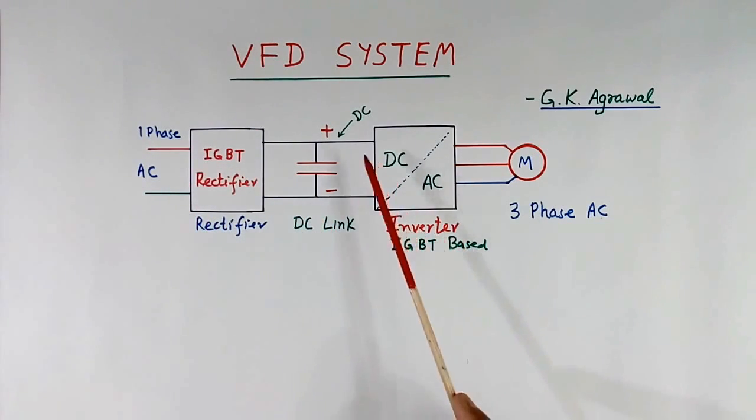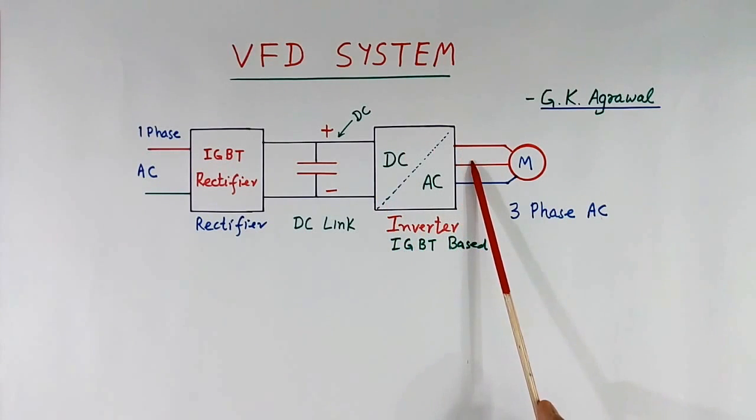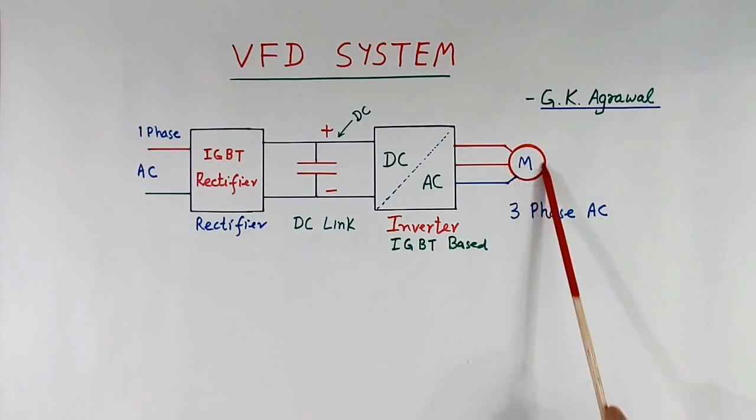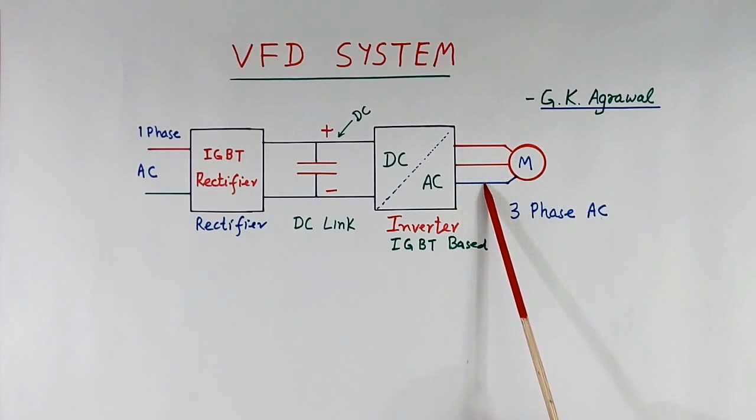Inverter converts DC into 3-phase AC. This also nowadays is made using IGBT. Now to control the motor speed, frequency of this AC supply needs to be controlled. That also is done by this inverter. So inverter does 2 jobs mainly. One is to make 3-phase AC supply. Second is to control the frequency. But in traction system, there will be so many controls, but simplest one is to control the frequency here to control the motor speed.